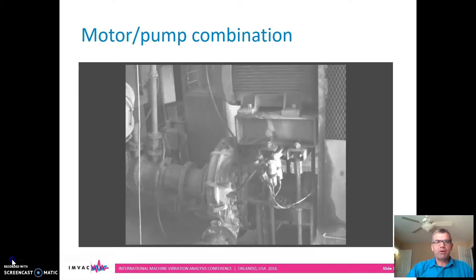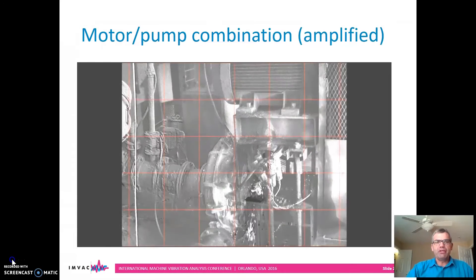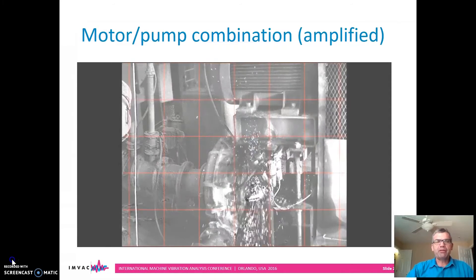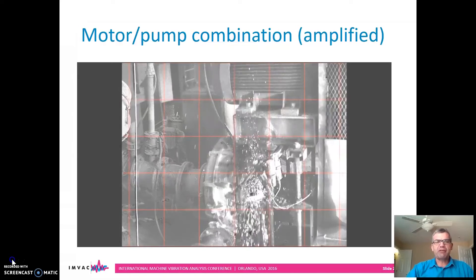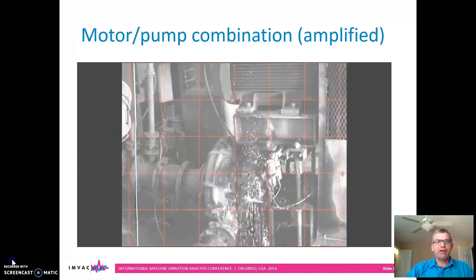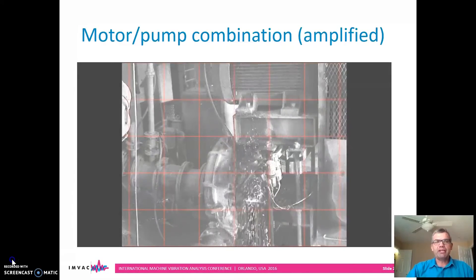Have a look at this motor-pump combination operating in a platinum concentrator. Even though there's no sound to the video, I can assure you it was making horrible noises and that motor was not doing well. If you amplify the motion in the video, you'll see that motor is just jumping up and down, shaking itself apart. It's also affecting the pump and the equipment right next to it.